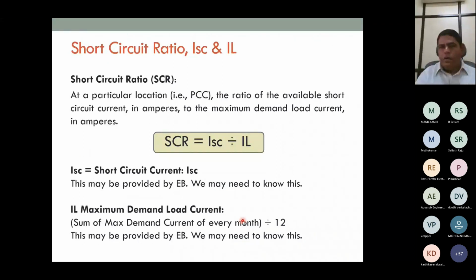Before going into current harmonic measurements, which is TDD, I'd like to share a very simple formula, which is called short circuit ratio. It is ISC divided by IL. ISC is nothing but the short circuit current at your meter point or at your PCC. So this we may have to get from the MRT people. And IL also, as it is measured on the HV side, we may have to get from them. It will be a 12-month average. So if the short circuit ratio is given by them, it is easy for us to find out which is our limit. I'll be showing in the next slide how this short circuit ratio will be used.